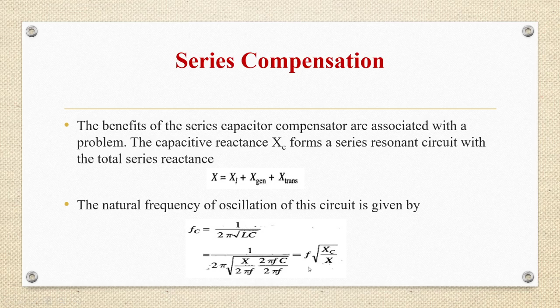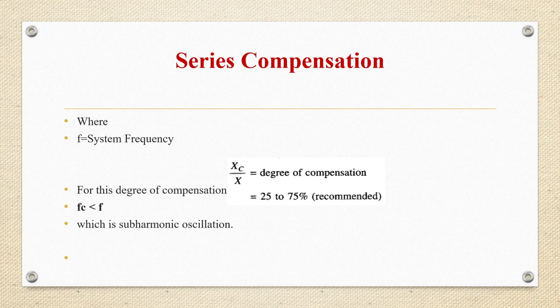That is f into root of Xc by X, where f is the system frequency and Xc by X is the degree of compensation, and for this degree of compensation 25 to 75% is recommended, and Fc is less than f, which is subharmonic oscillation. So even though series compensation has often been found to be cost effective compared to shunt compensation, but sustained oscillations below the fundamental system frequency will cause the phenomena referred to as subsynchronous resonance.